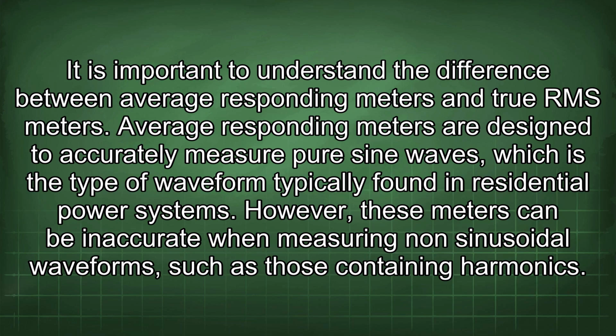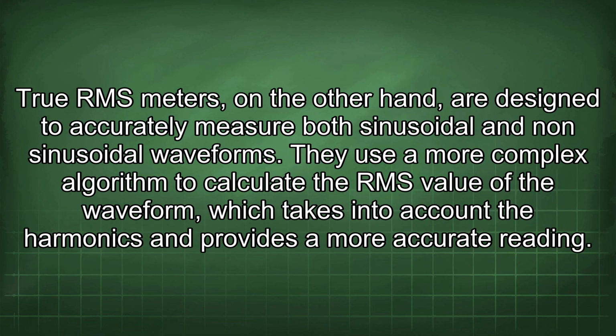It is important to understand the difference between average responding meters and true RMS meters. Average responding meters are designed to accurately measure pure sine waves, which is the type of waveform typically found in residential power systems. However, these meters can be inaccurate when measuring non-sinusoidal waveforms, such as those containing harmonics. True RMS meters, on the other hand, are designed to accurately measure both sinusoidal and non-sinusoidal waveforms. They use a more complex algorithm to calculate the RMS value of the waveform, which takes into account the harmonics and provides a more accurate reading.